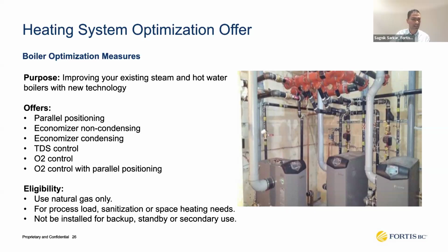Next is TDS control. TDS is total dissolved solids. It's just like checking the salt level in your soup. If there's too much salt in your soup, you won't like the soup, right? Same with the boiler. Usually hot water heaters or boilers do not like any salt in them. So you install a TDS monitor, which monitors the TDS level inside your boiler, and it is frequently blown down. What that means is that the water in the boiler system is being drained and fresh water is being added to it. So this keeps the boiler healthy.